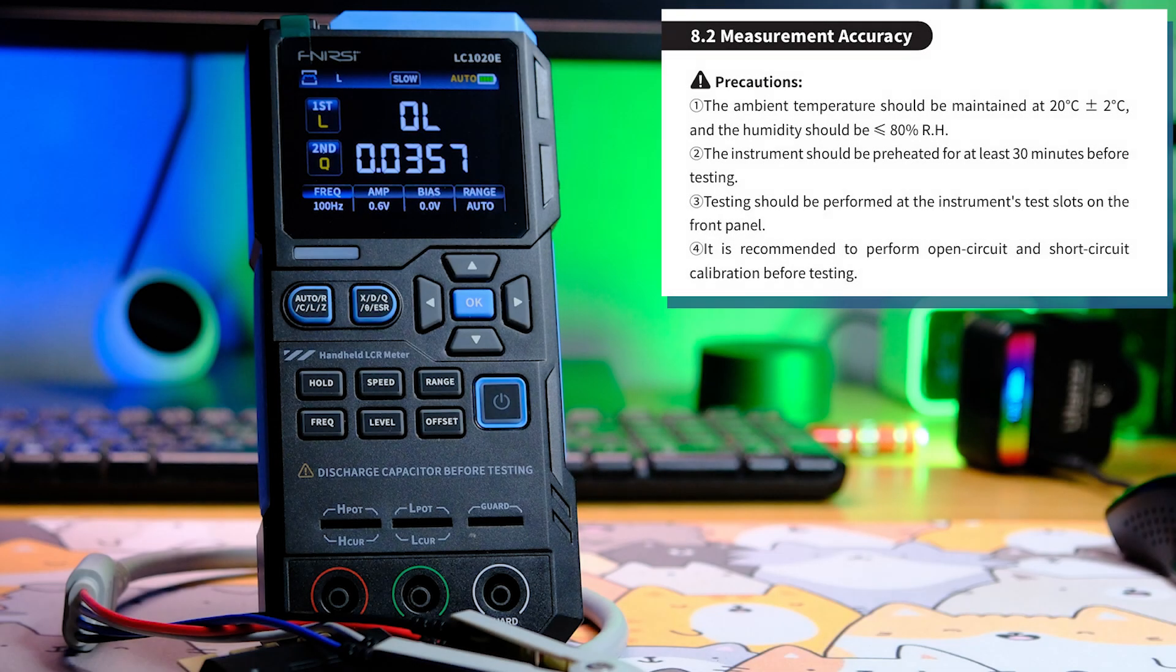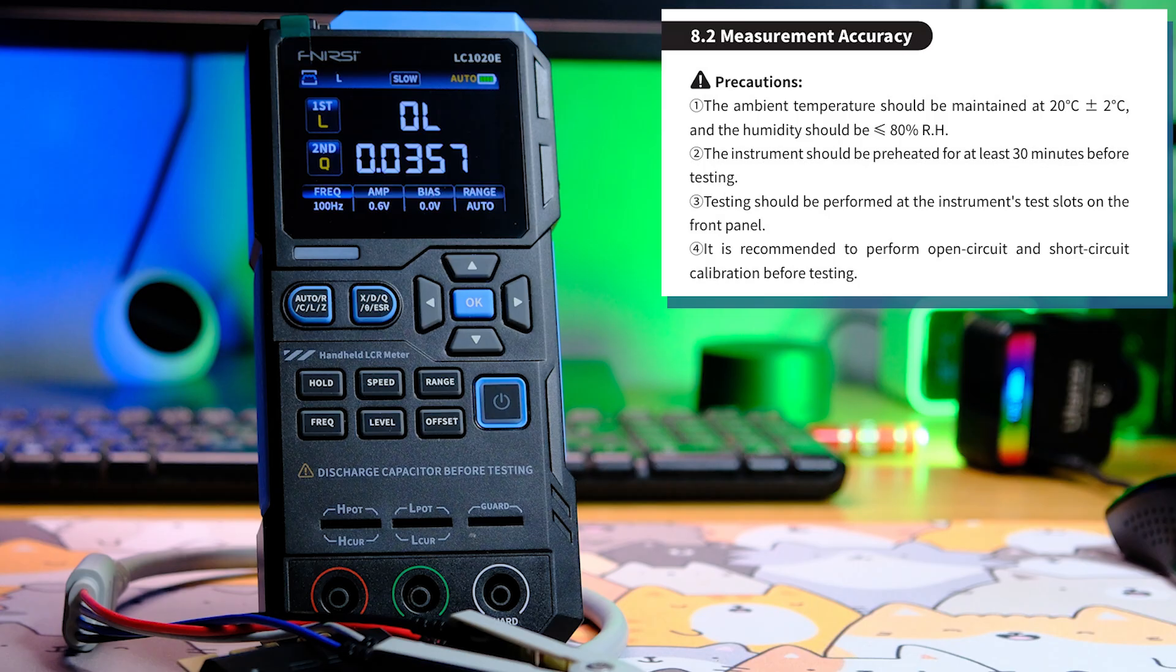The instruction manual lists operating conditions for the device. It should be used at a temperature of 20 degrees Celsius plus or minus 2 degrees. Right now, I'm in the studio at 28 degrees Celsius, so there's a chance the measurements may not be very accurate. Before using the tool, it must be warmed up for at least 30 minutes. I'm not going to do that either. I'll measure immediately.